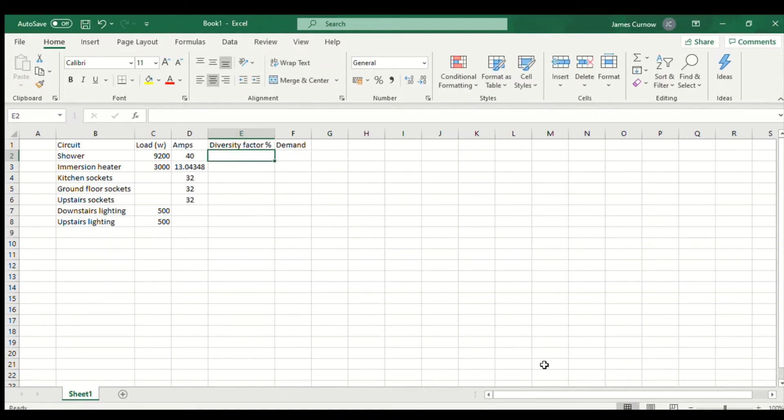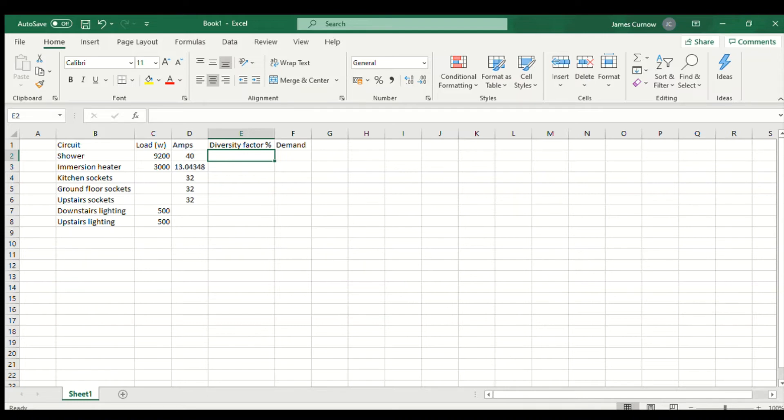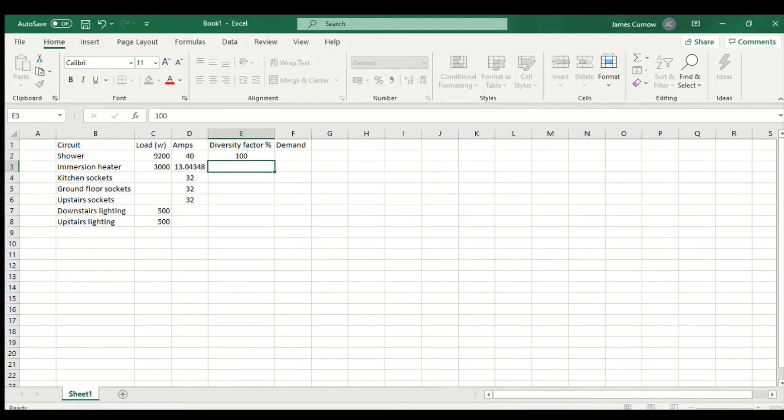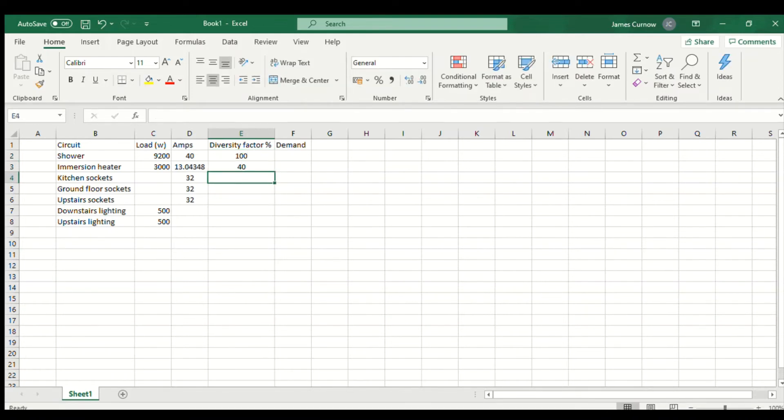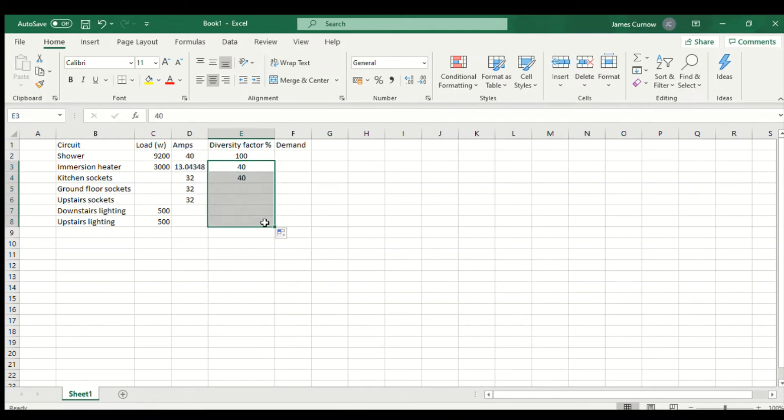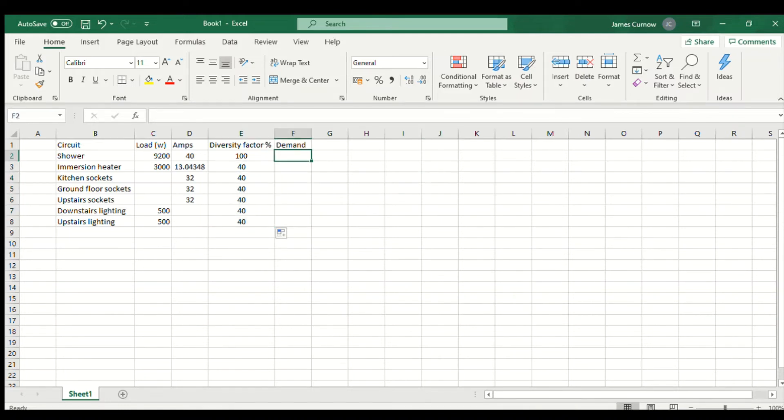Here I'm going to show what diversity factor I've used. For this example where we are using the method for circuits in accordance with Appendix H, it's 100% of the largest load and then 40% of each of the remaining loads.